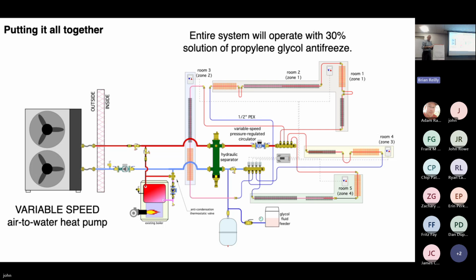It's not sounding like it's good for a retrofit. It's possible, but it's expensive. A good fan coil with a condensate drain, nominal $1,000, $900. Okay. It's getting all that infrastructure to it, that insulated PEX, the power, the condensate drain. So what level of insulation do you need on those PEX lines? Half-inch foam, half-inch elastomeric foam, Armaflex or something like that. That's fine. If you were in a greenhouse, you had super high humidity, something like that, you might go to 3/4 inch, but half-inch is fine for condensation control.